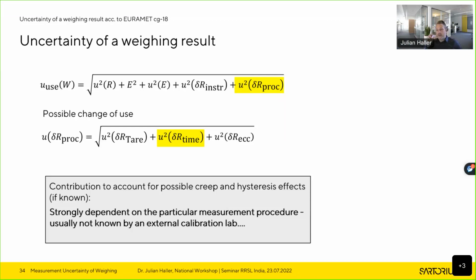As mentioned, I think this is really a difference between Europe and India: in Europe, let's say 80% of the weighing instruments that we sell are not for legal metrology. So the majority is not for legal metrology, and this is really applied metrology. It does not care about e or the class. You will find in the CG18 some information if the balance does have an e value, or if there is a class, but usually this is really applied metrology, so this works on any weighing instrument, even if it is non-verified.